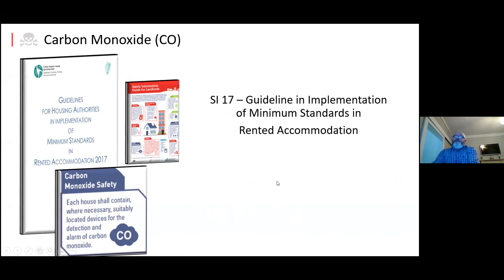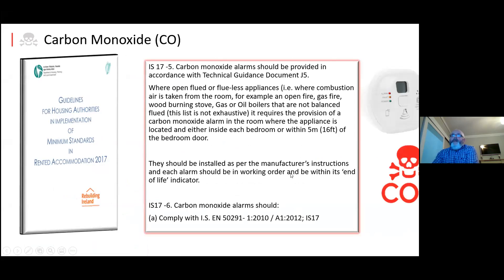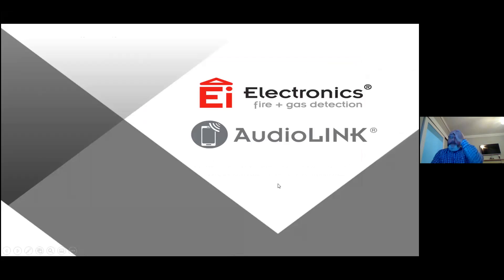SI 17 — the guidelines for rental accommodation — is very straightforward. Part J says 'where a new or replacement.' In rental accommodation it goes straight in: where open-flued or flueless appliances where combustion air is taken from the room — for example open fires, gas fires, wood stoves — it requires a provision of a CO alarm in the room where the appliance is located and either inside each bedroom or within five meters of any bedroom door. So it's straight in, no ifs, buts, or maybes: if it's rental accommodation with open fires, gas fires, or wood-burning stoves, you require a CO alarm. This should be installed as per the manufacturer's instructions.